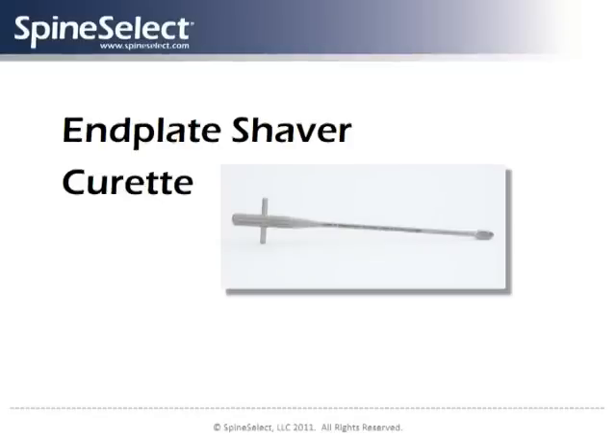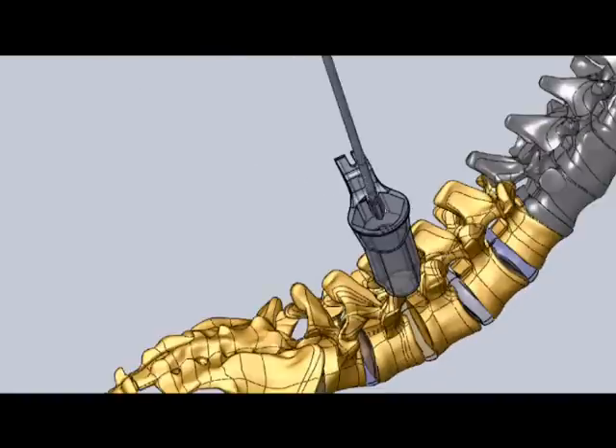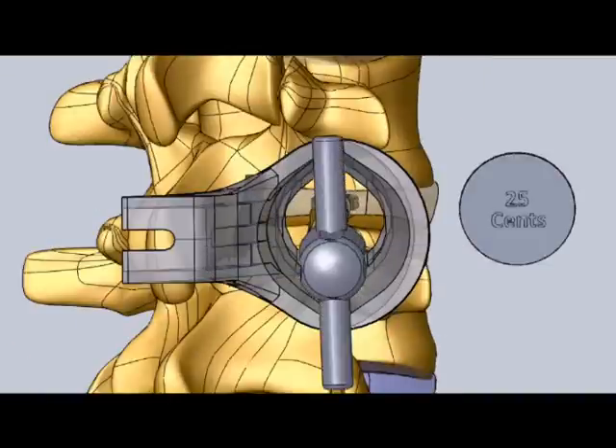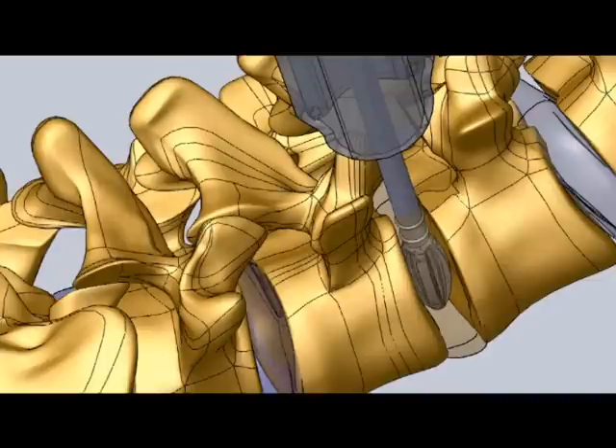The SpineSelect endplate shaver curette provides a particularly useful instrument to safely access the disc space without requiring nerve root retraction. The endplate shaver provides cutting action when rotated by the surgeon to help remove disc and endplate cartilage material.